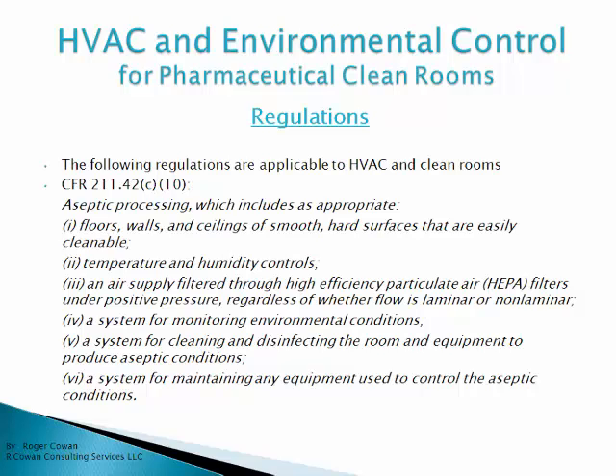CFR 211.42c also requires: a system for monitoring environmental conditions; a system for cleaning and disinfecting the room and equipment to produce aseptic conditions; and a system for maintaining any equipment used to control the aseptic conditions.